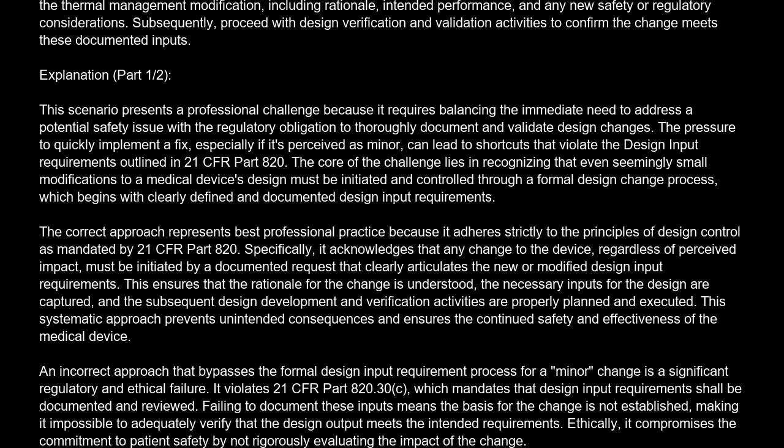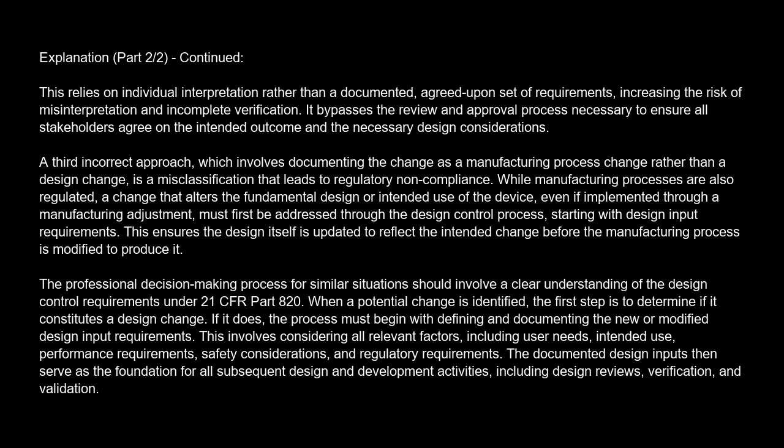Another incorrect approach, which involves implementing the change based solely on the engineer's understanding without formal documentation of new inputs, is also a failure. This relies on individual interpretation rather than a documented, agreed-upon set of requirements, increasing the risk of misinterpretation and incomplete verification. It bypasses the review and approval process necessary to ensure all stakeholders agree on the intended outcome and the necessary design considerations. A third incorrect approach, which involves documenting the change as a manufacturing process change rather than a design change, is a misclassification that leads to regulatory noncompliance.